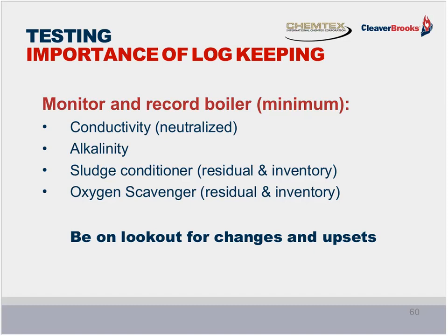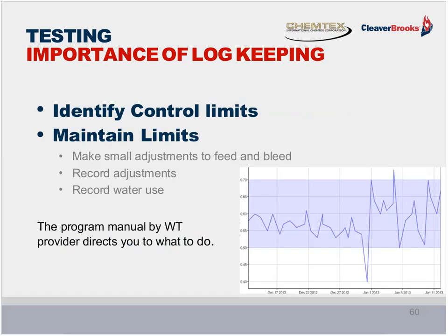While you're looking at changes and upsets, you want to immediately be thinking about cause and effect. In this particular example, you've identified that your system is out of limits and you want to move it back into limits. You want to make small adjustments to the bleed and feed of the system generally, and you want to record those adjustments and record the water use so that you know what you've done to make sure that the program stays in line.